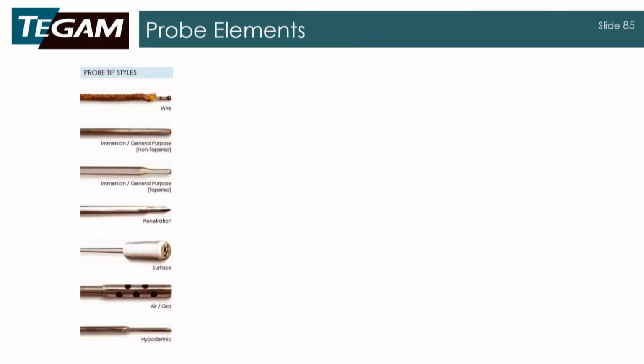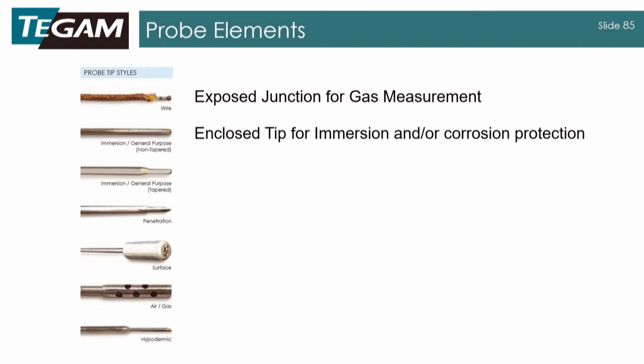All right, so here's basically an overview of different types of probe elements. As you saw, there's the wire probe, exposed junction, usually for air measurement. A lot of times, I don't know if you guys do any car work or anything like that, but if you get one of those Craftsman voltmeters, if they throw in a temperature probe, it's going to be a wire probe like this. You can push it up against things and get general temperatures, but a good rule of thumb is that if it's an exposed junction, it's mainly for gas measurement. This is an enclosed tip for an immersion probe, also helps with corrosion protection. That was the second type that I was using there. This is an immersion probe with a tapered tip, and because it has that tapered tip, there's less surface area, so you get a faster response time out of it.